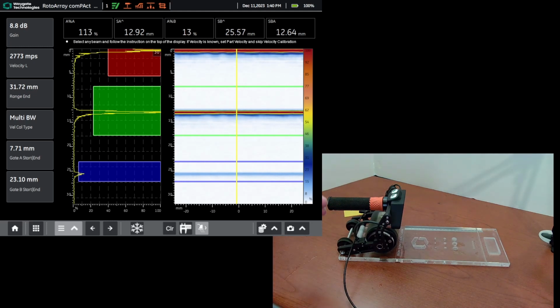As we scan across the face of the probe, we want each one of the individual beams to be giving us the same amplitude of indication from the same reflector. So we'll set that up first. Then we'll check our encoder calibration, our distance encoder calibration. Then we'll do a simple line scan.